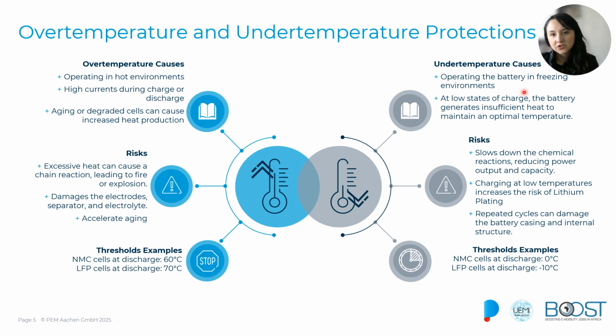In this case, these protections are triggered when the battery operates below its minimum safe temperature, and typically this happens in freezing environments at very low temperature. What happens when we operate the battery at such low temperatures is that the chemical reactions in the battery slow down, and one of the effects is that this will reduce the battery power output. But this can also damage our battery during charging. If we charge our batteries at very low temperatures, we have the risk of lithium plating, which might lead in the end to internal short circuits and permanent damage in our batteries. The mechanical stress at low temperatures also has to be considered, because the battery casing and the internal structures can get damaged because of the low temperatures.